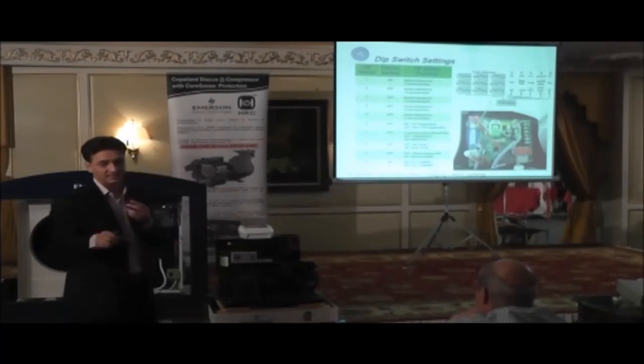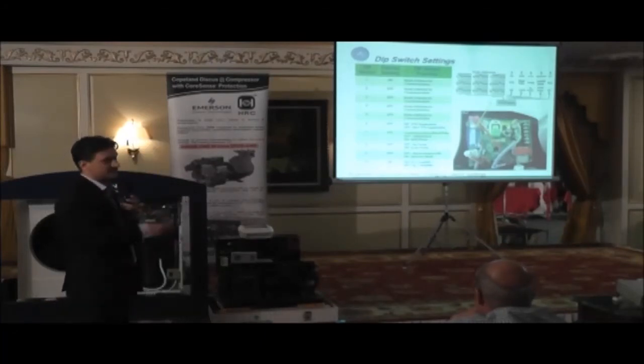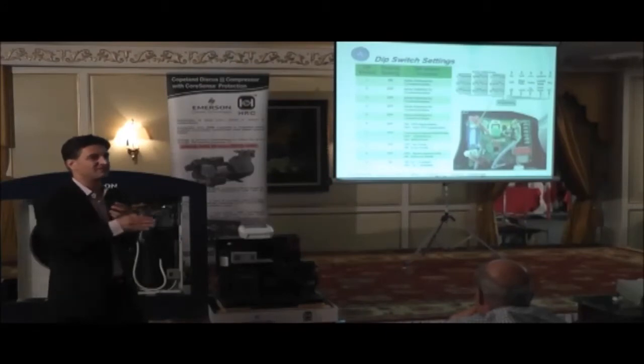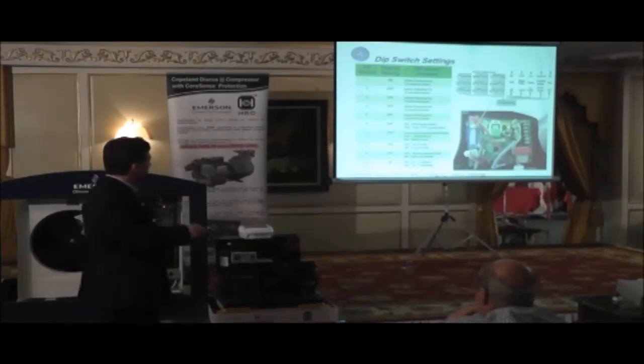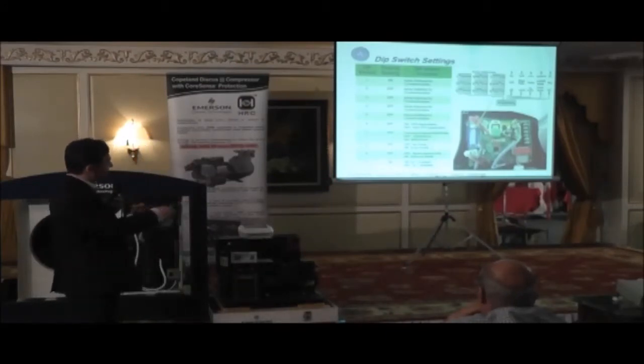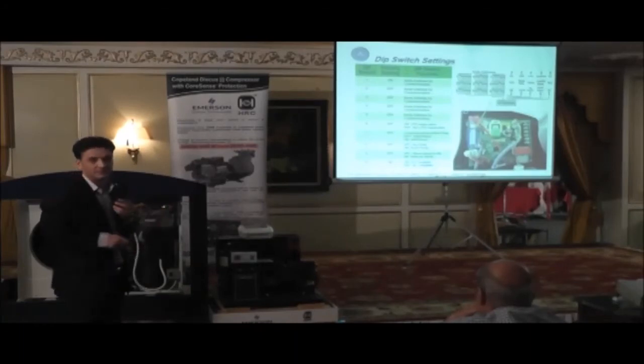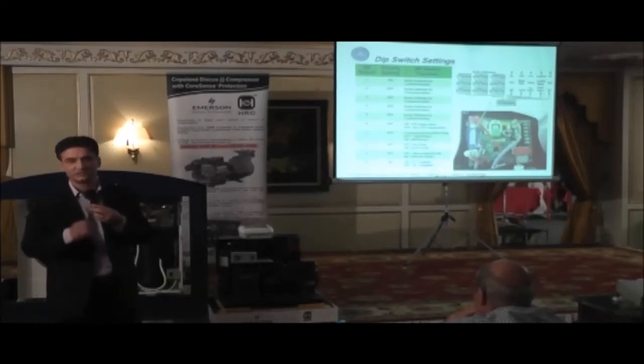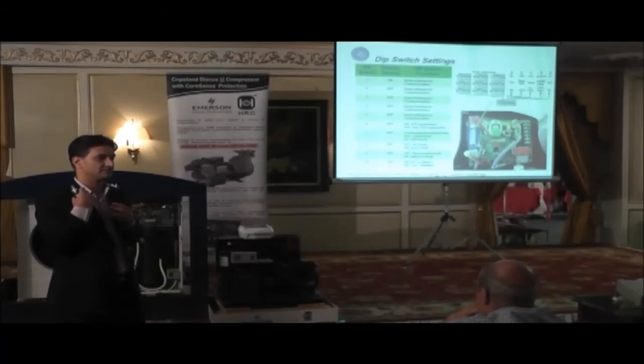So if you use it in this application, for each compressor that you have on that rack, you've got to have a device address. So you would use dip switches 1 through 5 to set the address of that compressor so that the controller can pick it up. Okay?